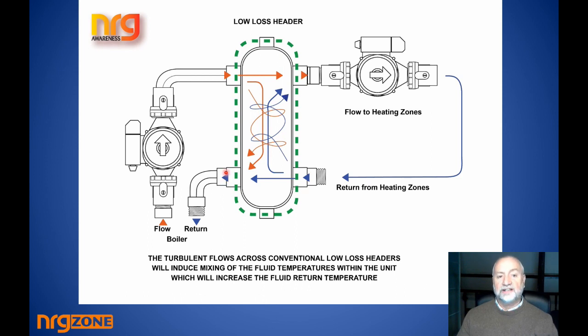But of course, in this advent of heat pumps and condensing boilers, the last thing we want to do is heat the return water, because if you're heating the return water, you're preventing the extra efficiency that comes through heat pumps and condensing boilers from the condensation idea. And condensation can be upwards of 25% additional heat gain depending on how it's organized within the system. So it's a substantial thing to ignore.